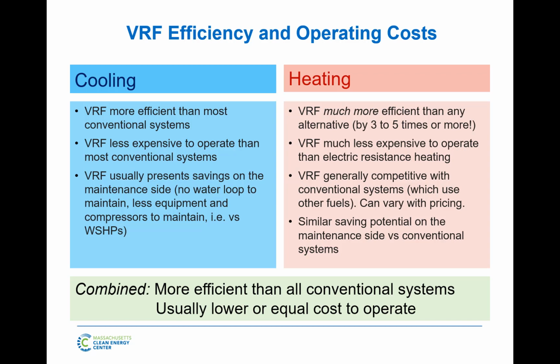Now in heating, we talked about VRF being much more efficient than almost any systems by 3 or 5 times. That's the COP. But we're cheaper to run than electric resistance heating. But we use electricity, not gas. So overall, the discussion about what's cheaper to run in the winter between VRF and conventional systems is that discussion about transition temperatures and costs of gas and electricity. Overall, in our market, VRF is going to win or be on par with conventional gas-fired systems, traditional efficient gas-fired systems, with the temperatures that we have and the electricity prices that we have. As soon as gas goes up, or as soon as electricity stabilizes or goes down, that number gets better. The opposite happens, that number gets worse.